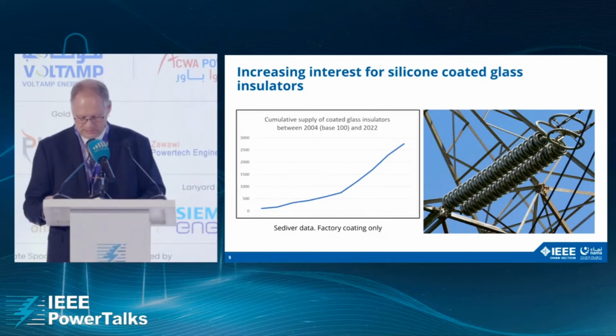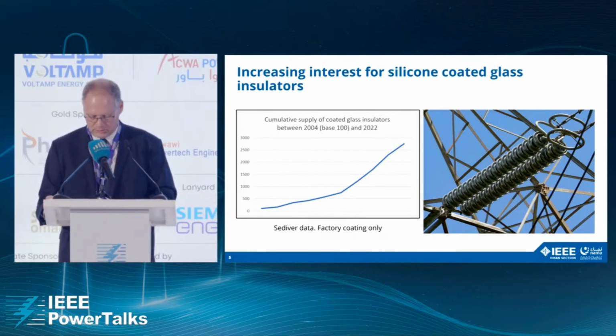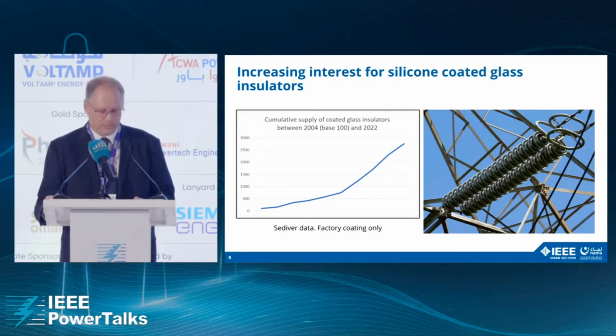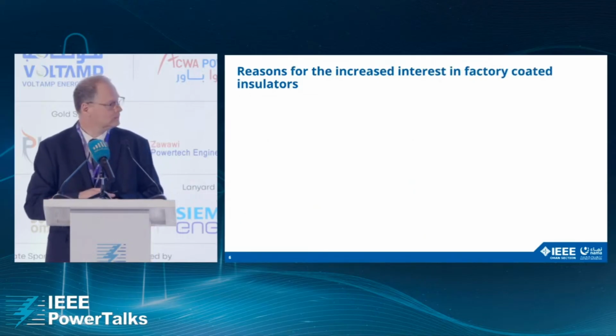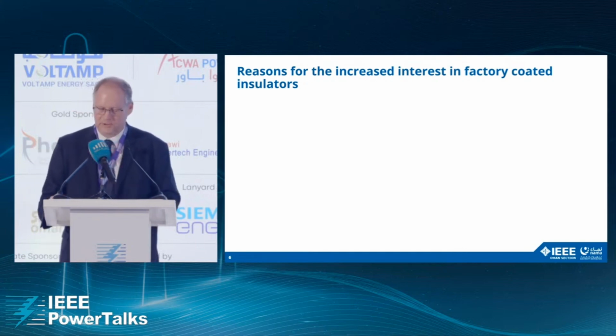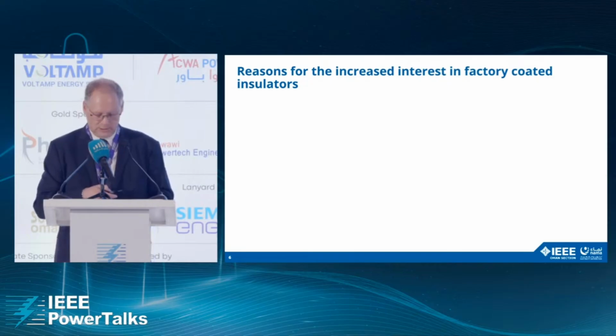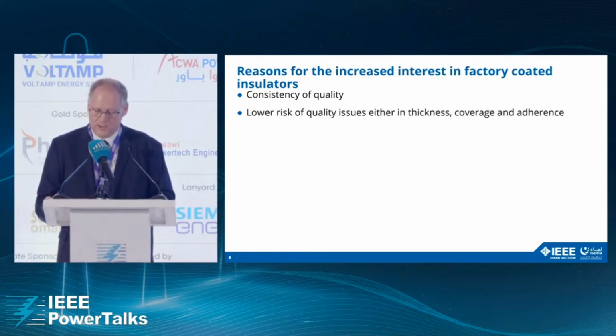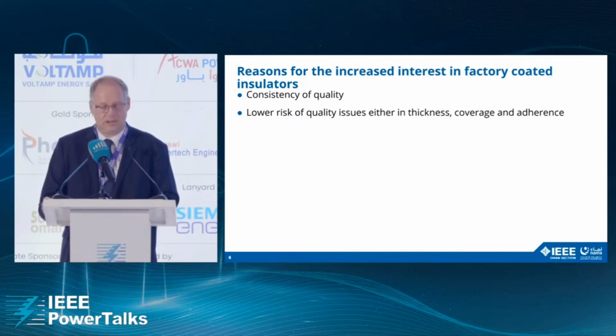As an illustration of this growing demand, the graph shows the actual trend seen by Sediver in the development of silicone-coated glass insulators. These numbers are based on our experience, and they show growth of 30 times over a period of approximately 20 years. The big interest for this kind of product is the ability to give to glass insulators the pollution performance of polymer insulator without the risk inherent to polymer. The main advantages of factory-coated insulators are consistency of quality, lower risk of quality issues, either in thickness, coverage, and adherence on the glass surface.